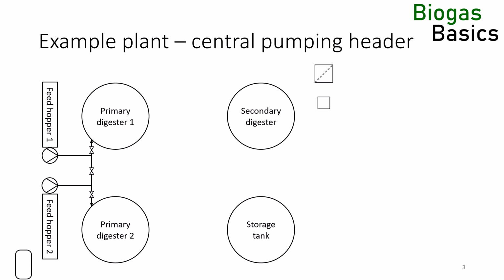Often, this comes in the form of a pumping container manufactured in a workshop and shipped to site for installation. This pumping system is prevalent on small agricultural biogas plants. The general idea is to have two large header pipes and connect every tank to the suction and discharge header. A pump connects the two headers. A standby pump can be installed parallel to the duty pump to guarantee high uptimes of the biogas plant.